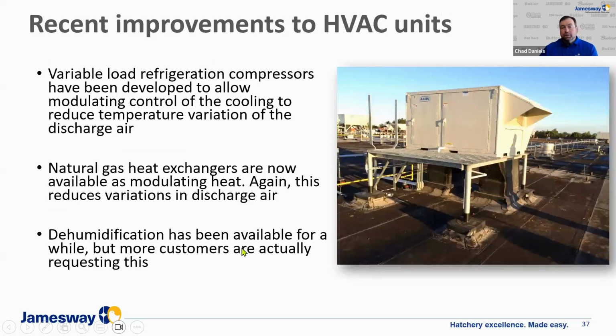Some advancements have been made with rooftop HVAC units. I'm not trying to tell you to go buy this system brand new to put on a hatchery, but if you do have existing units and you have to replace them, you need to consider some of these new options. One is variable load refrigeration compressors. That allows you to have some variable control of the discharge air temperature when the HVAC unit is cooling, which will help avoid some of those big swings in temperature. In addition, natural gas heat can also be purchased with modulating, so again, trying to control that discharge air.